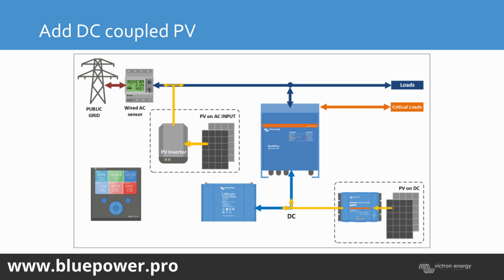Yeah, so if the BMS disconnects, you're still going to have a problem. So that's why you must program your system correctly so that it disconnects before the BMS switches off. Because if your BMS switches off, you're going to have to apply a voltage source onto that.